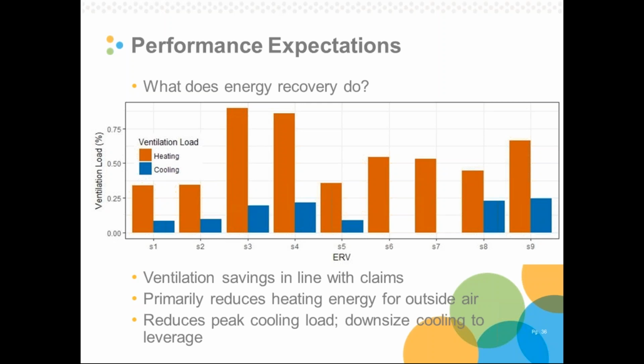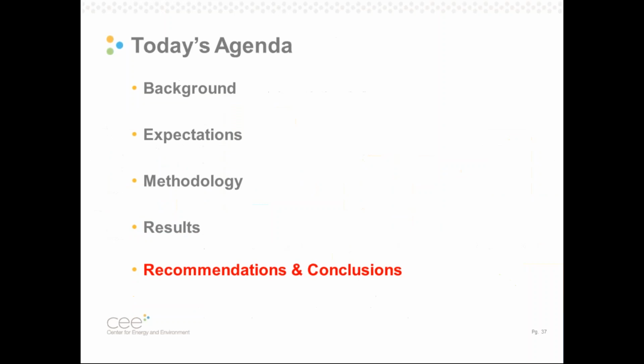So really the opportunity on the cooling side is at the peak load. That's where the loads are large and we can get maybe 20 to 40% reduction in peak load, which if leveraged allows us to downsize cooling equipment, and that's really the benefit in Minnesota. So heating savings and peak cooling reduction. That's why we implement energy recovery in Minnesota.